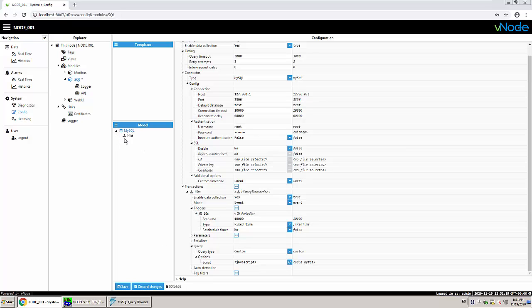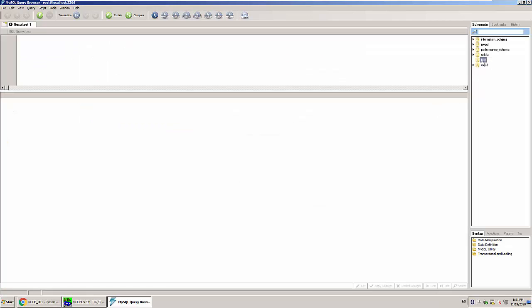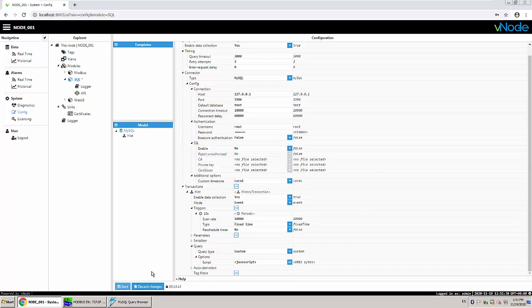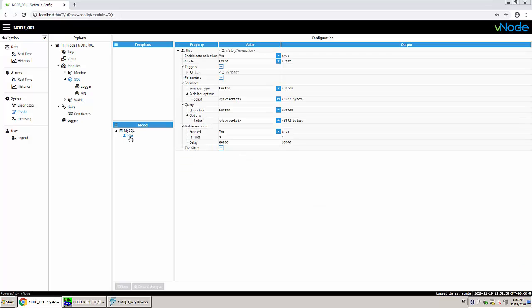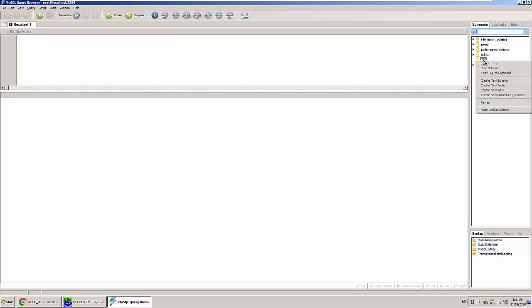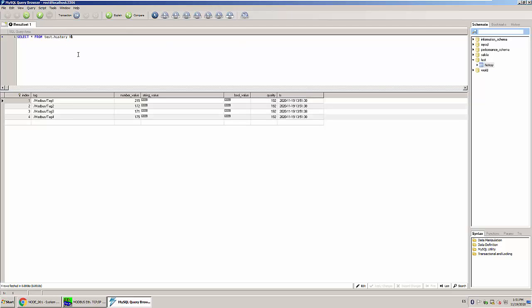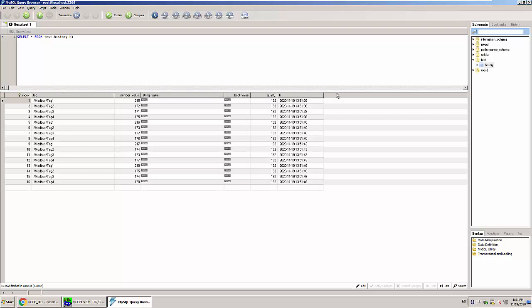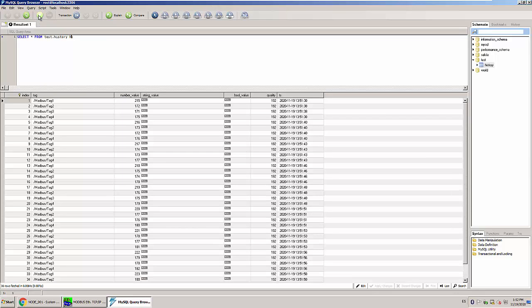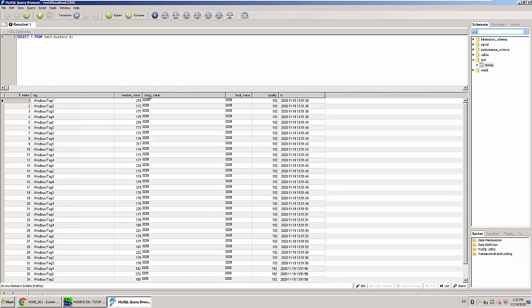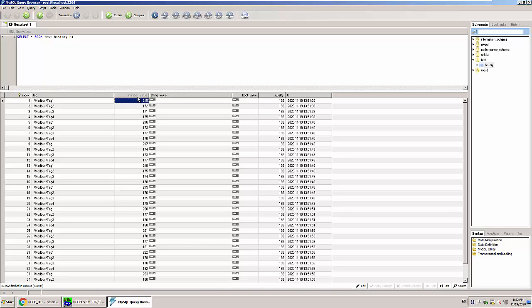When I press save, a new table called history is created inside the test database and my four tags will start filling it. I press save and restart the module. If I go to test in the query browser and refresh, I have the history table. Checking what's inside, I can see my tags changing — as shown by the timestamps — and the values are being sent to the number value column.